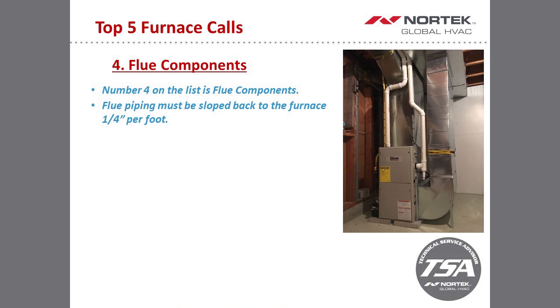Also, we get questions on what is approved piping material. So we have 8 different approved piping materials for our high efficiency furnaces. The most common piping material that is used is schedule 40 PVC. We also have the foam core PVC, which is approved as well. That's probably the most common piping materials that are used in the field. But there's a total of 8, and those can be found in the install instructions of the G7 furnace.